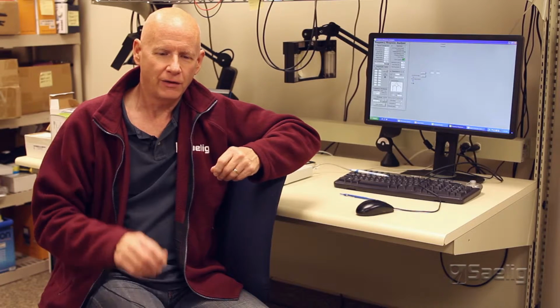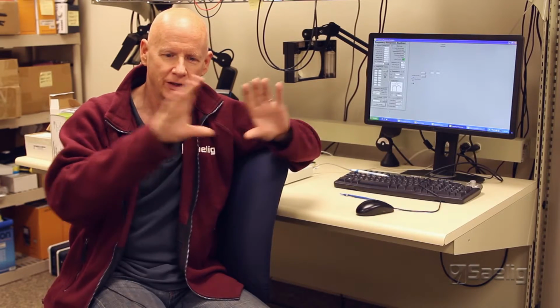So you're trying to design some kind of analog system or some filters, and you've got a certain bandwidth that you're interested in. So you can set up the FRA to sweep across that bandwidth of interest and give you the full picture of what the component is actually doing. The other thing that we'll demonstrate later is that you can develop a family of curves on the spectrum analyzer portion of this so that you can see how a bunch of the same type of component are all working. You can get an idea of the variance of the specification and also how the whole group of them is performing. So it's really very interesting to see all of that stuff.